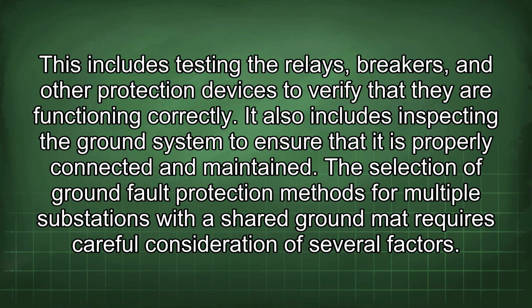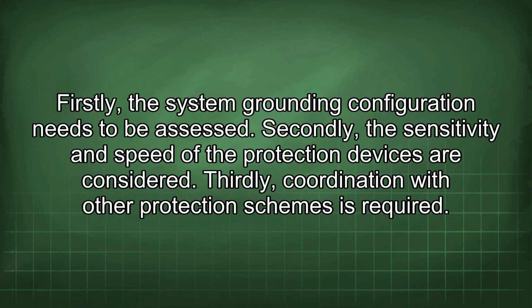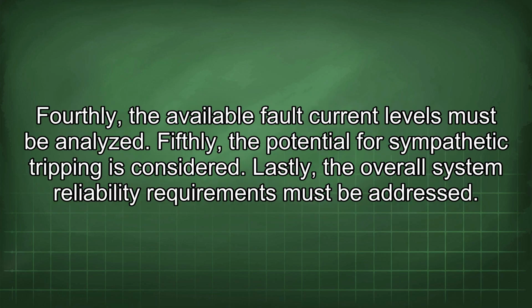The selection of ground fault protection methods for multiple substations with a shared ground mat requires careful consideration of several factors. Firstly, the system grounding configuration needs to be assessed. Secondly, the sensitivity and speed of the protection devices are considered. Thirdly, coordination with other protection schemes is required. Fourthly, the available fault current levels must be analyzed. Fifthly, the potential for sympathetic tripping is considered. Lastly, the overall system reliability requirements must be addressed.